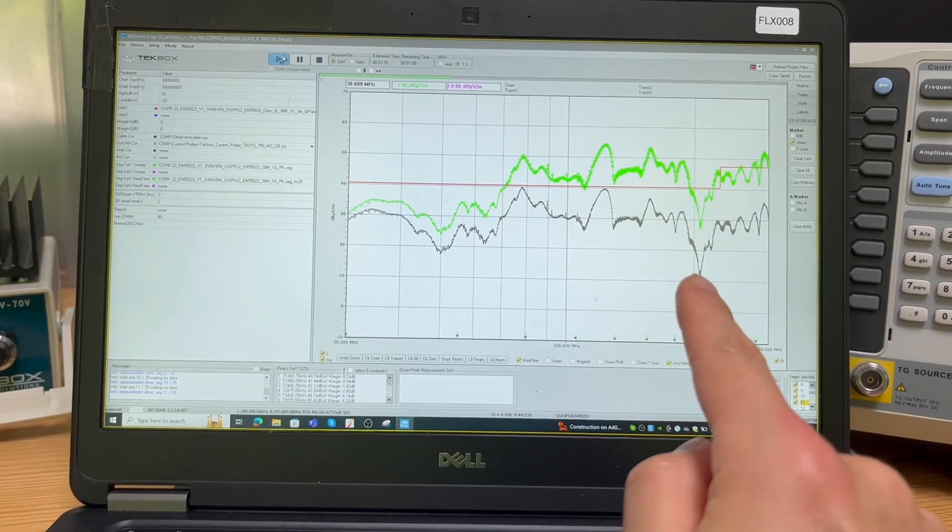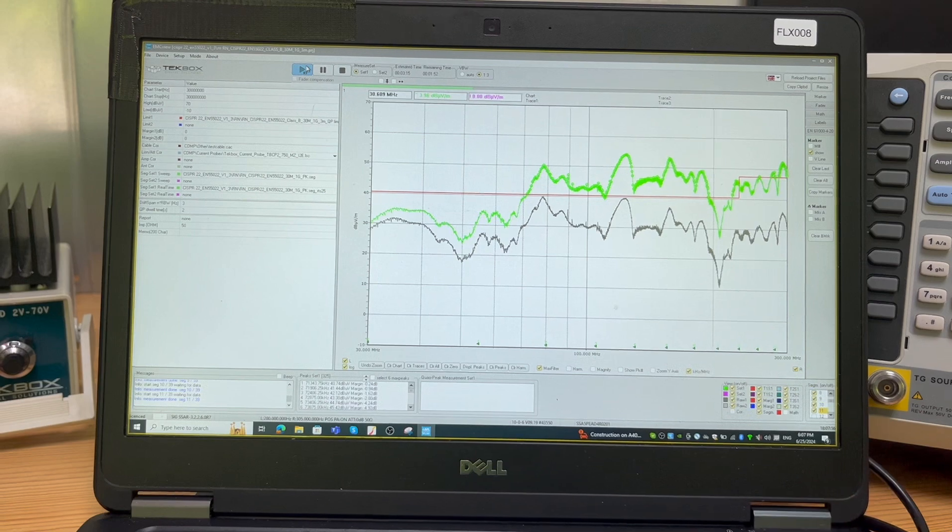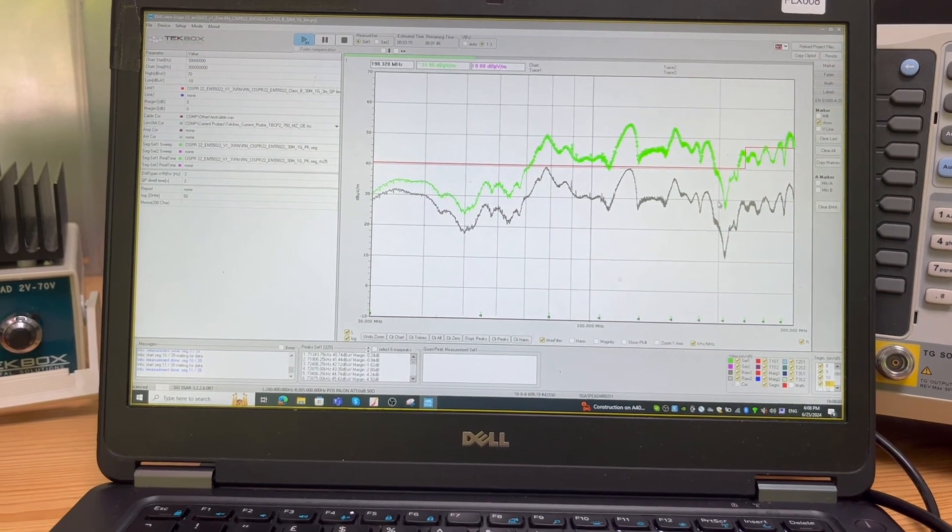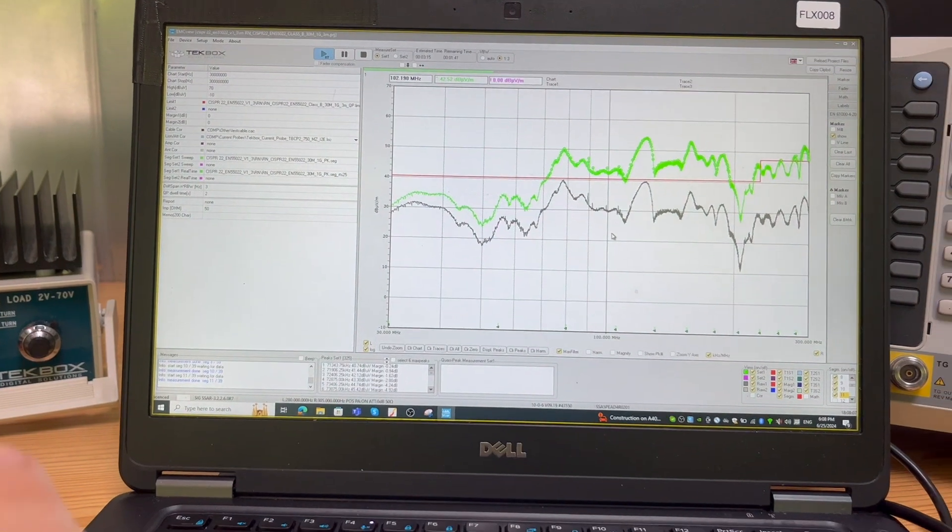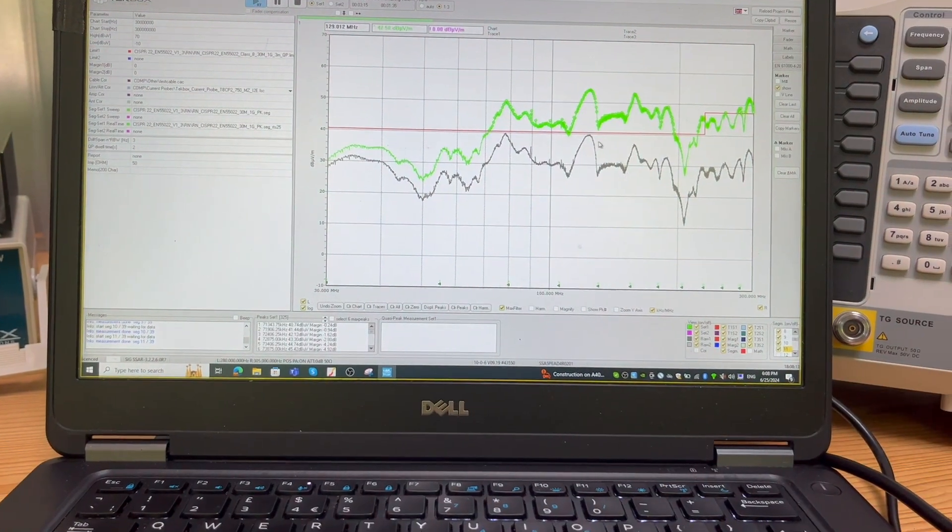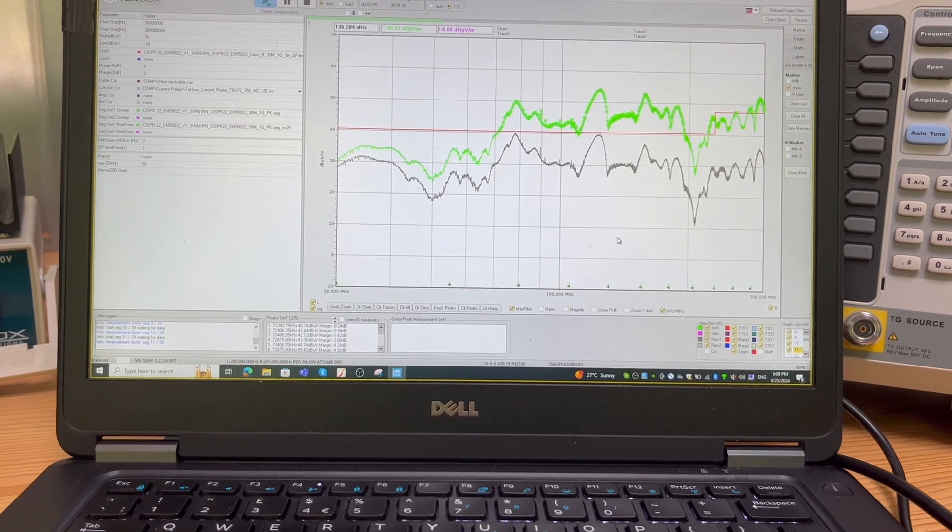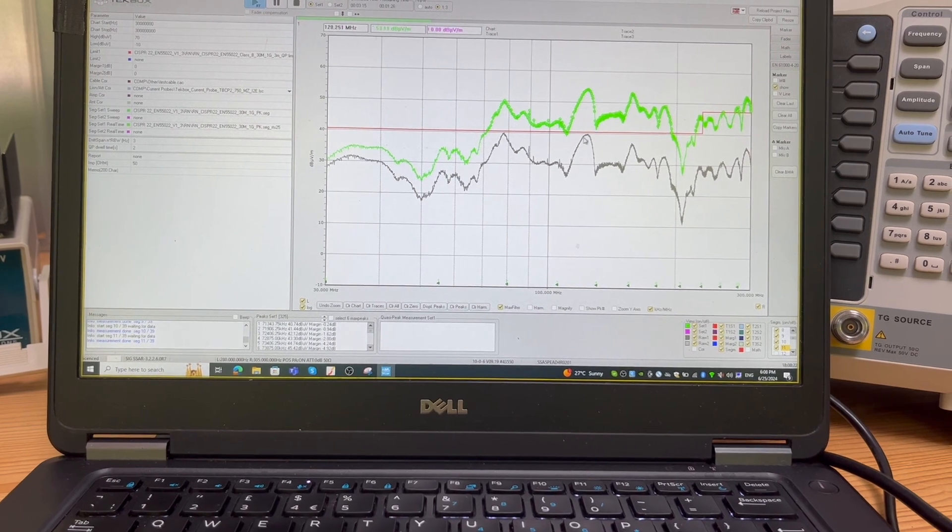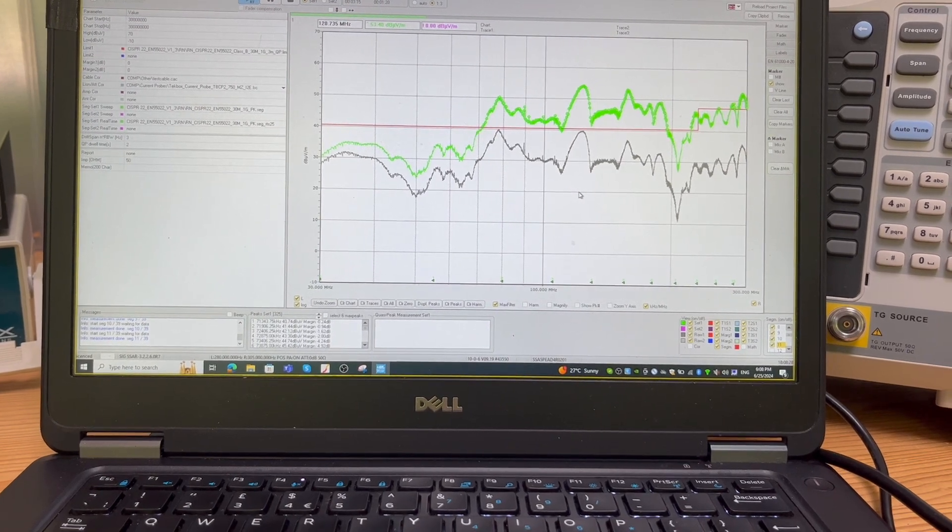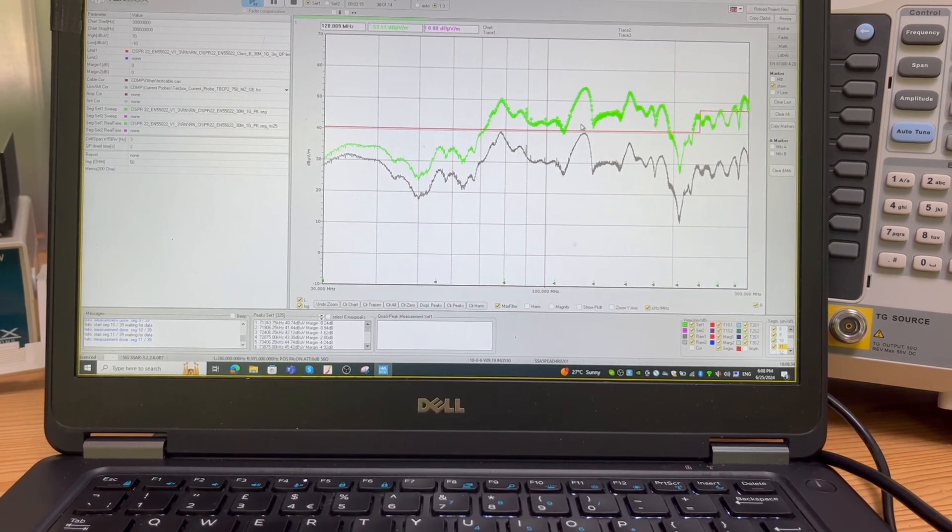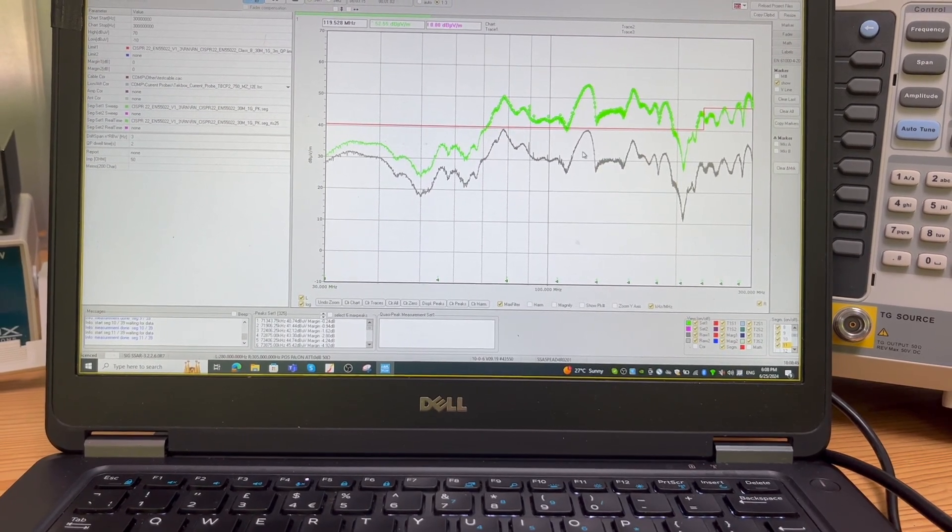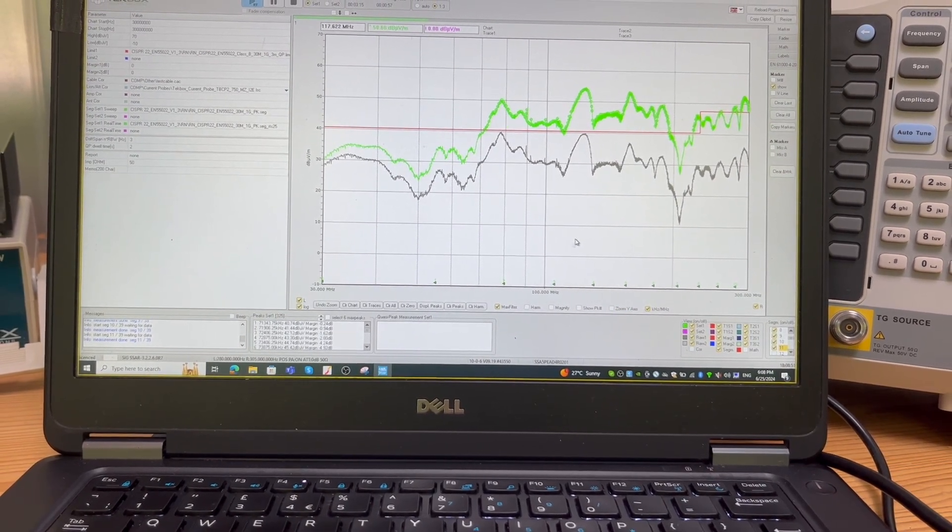If that's the case, this is dB microvolts showing in the raw data, and we know roughly speaking this TPCP2750 has 20 dB ohm as a transfer impedance. If we use this value minus 20, that means the dB microamps. In this case, for example, if we look at the current limit, 40 in this case, and this is hitting 40. If I minus 20, that gives me about 20 dB microamps. But 20 dB microamps means we'll fail this Class B limit, failing by 15 dB. In order to ensure a good pass, my measured RF current should really be about 5 dB microamps. Giving 5 dB microamps, I may pass.